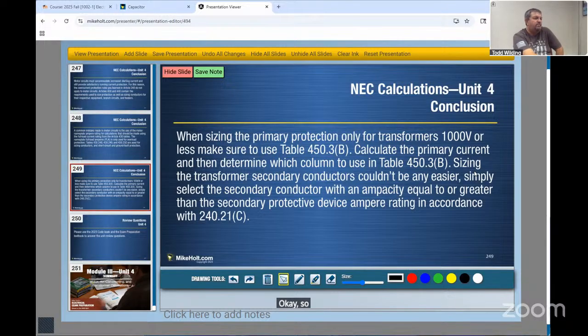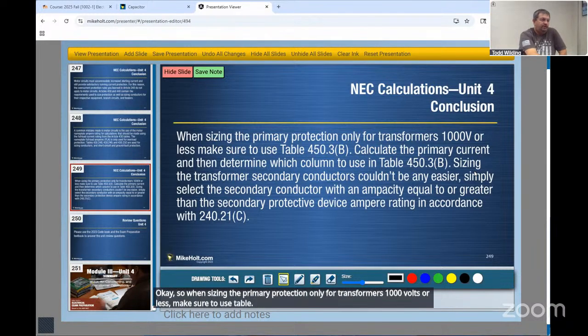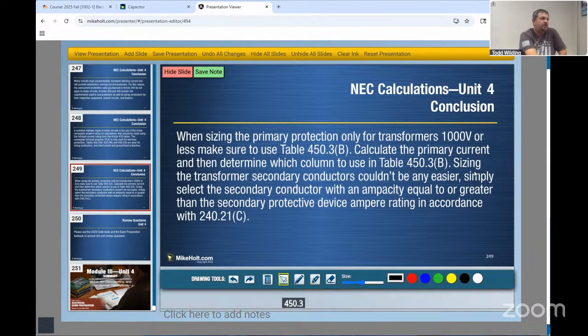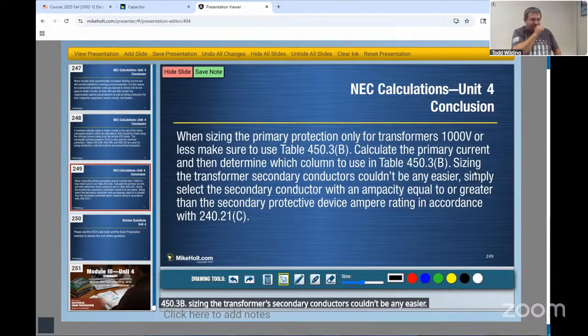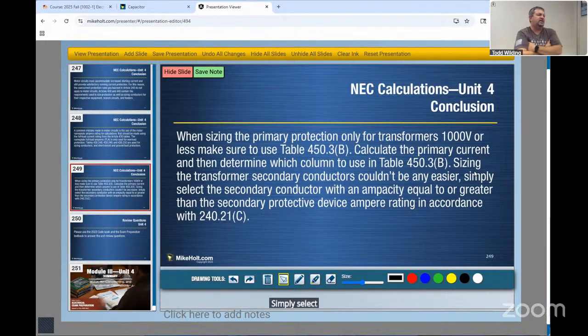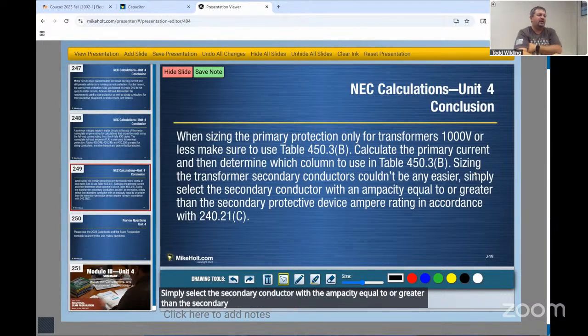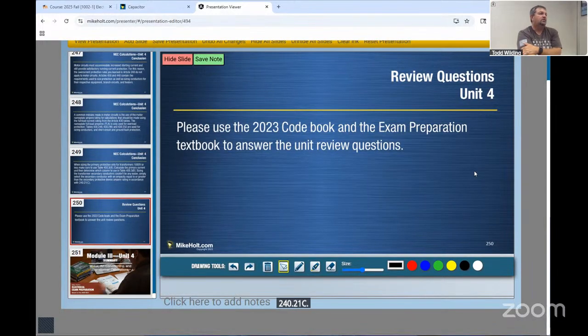Okay, so when sizing the primary protection only for transformers 1,000 volts or less, make sure to use table 450.3(B), calculate the primary current, and then determine which column to use. Sizing the transformer secondary conductors couldn't be any easier. Simply select the secondary conductor with the ampacity equal to or greater than the secondary protected device ampere rating in accordance with 240.21(C). Please use the 23 code book and exam prep textbook to answer the review questions.